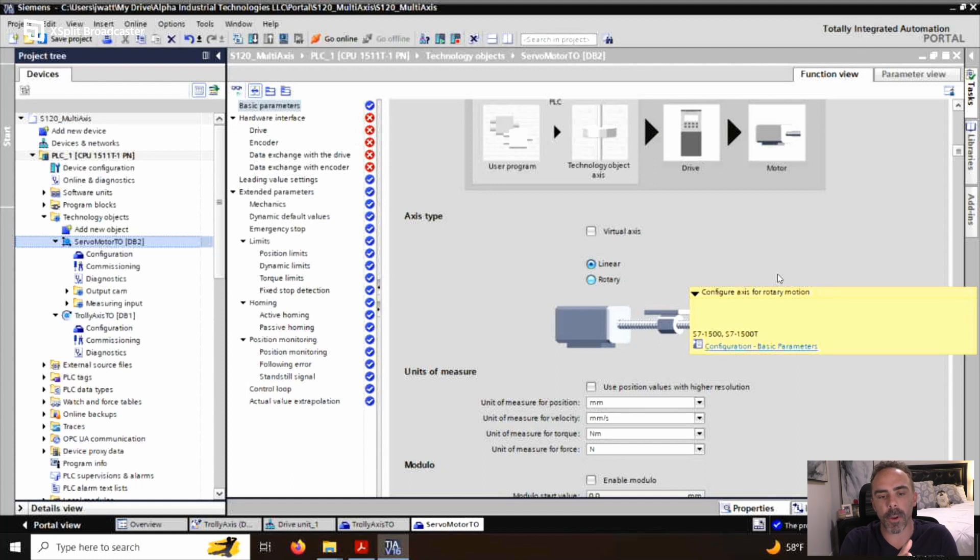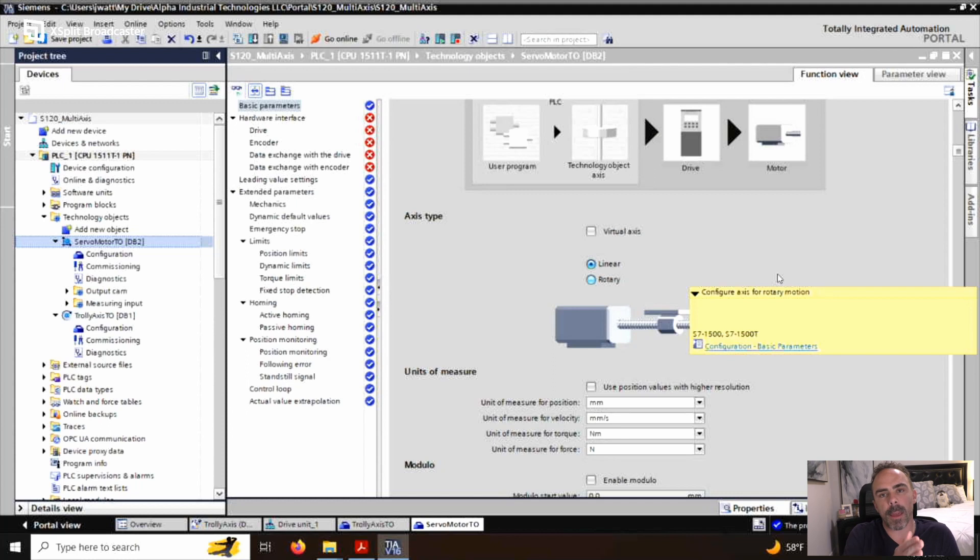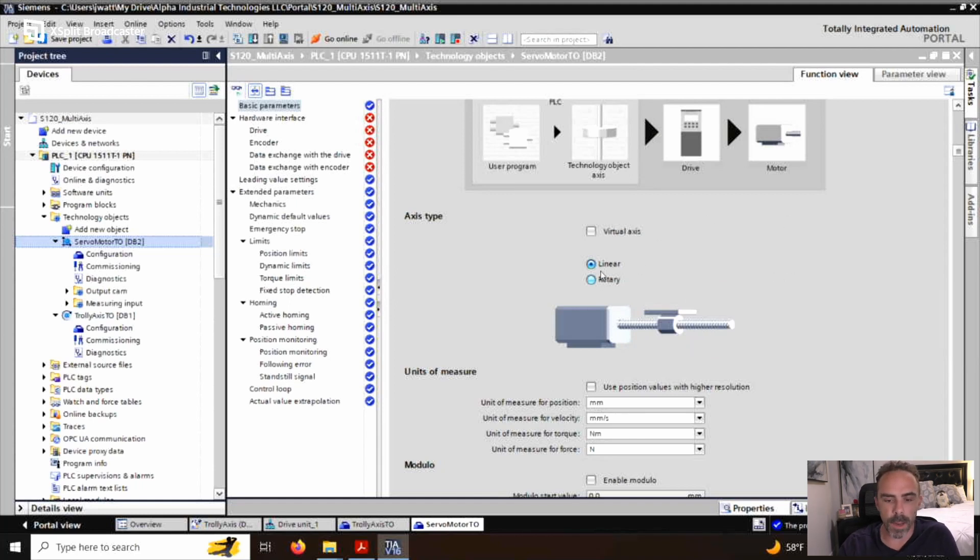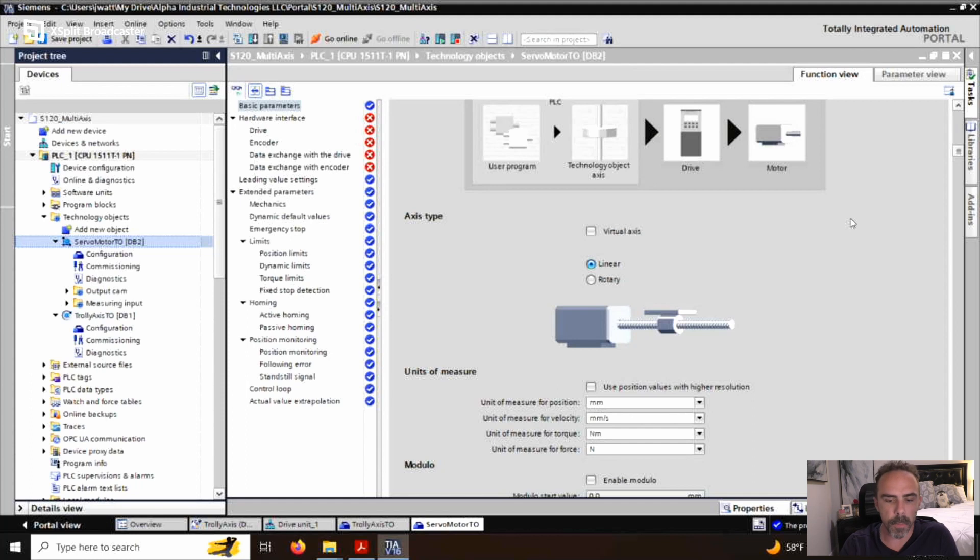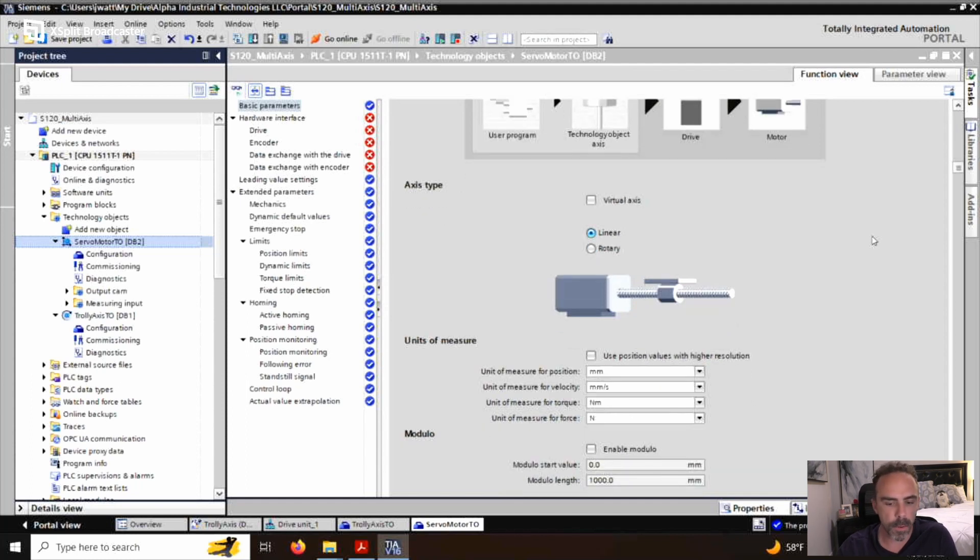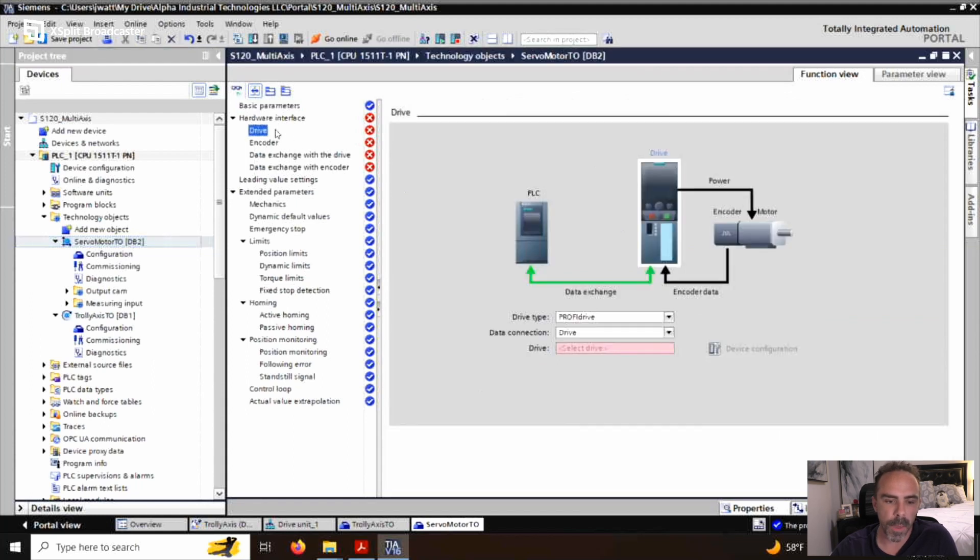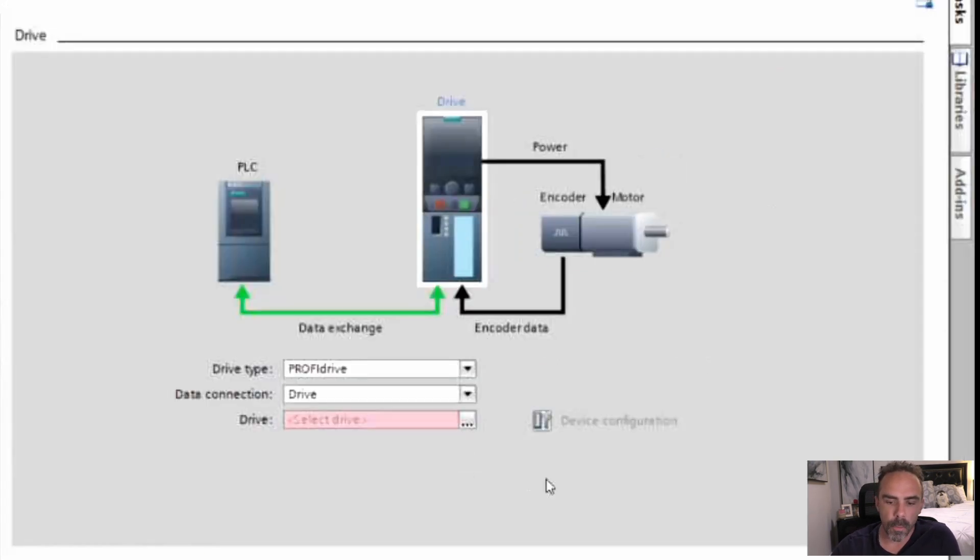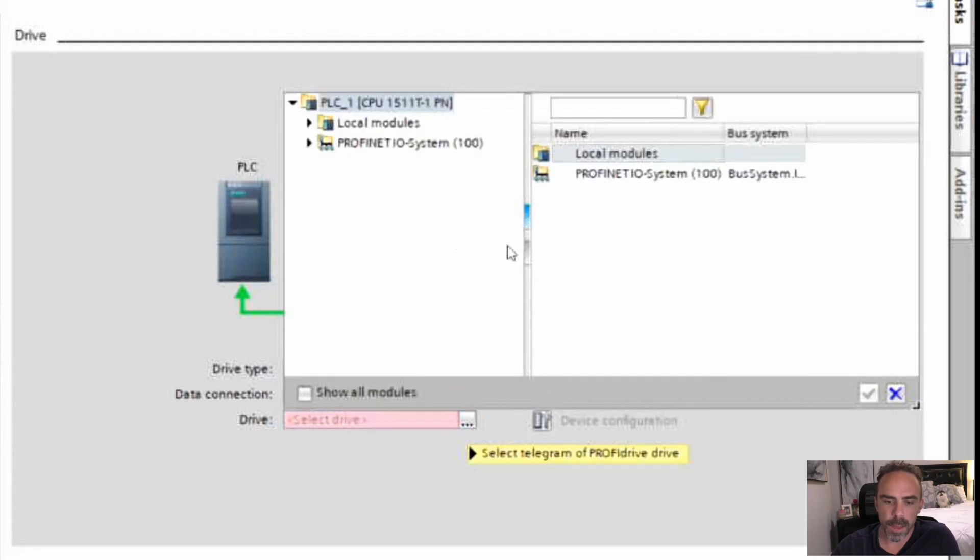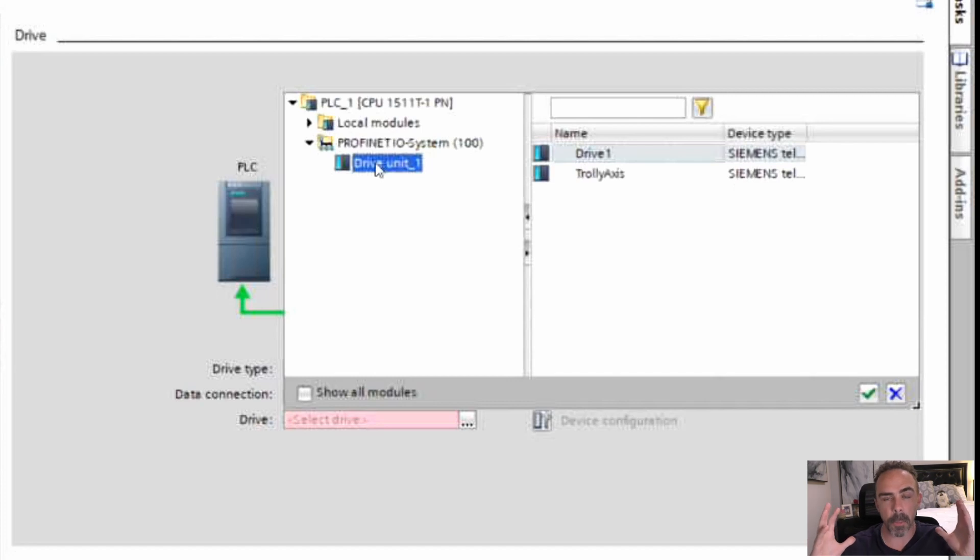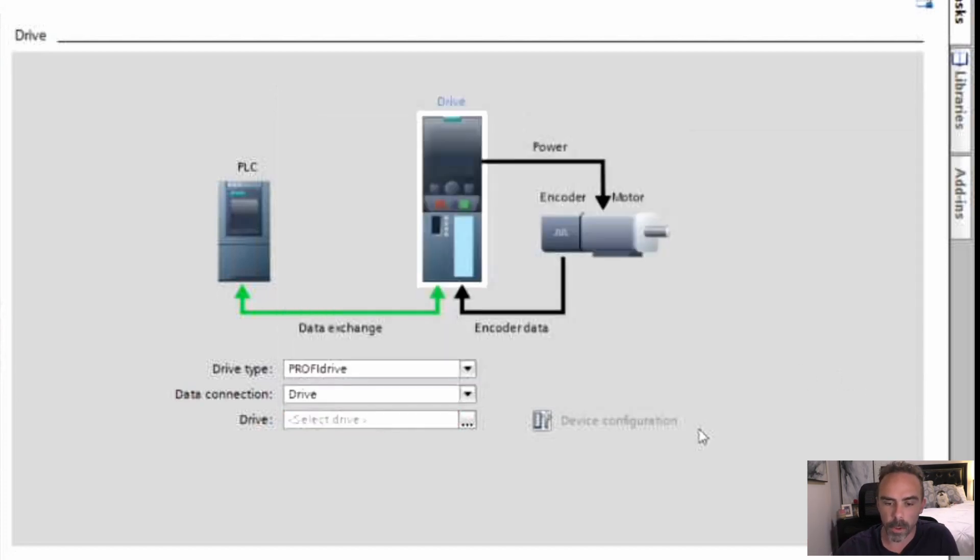One of the things about a positioning system is you need to know what type of motion you have. Are you going to be doing something in linear motion? Are you measuring something in millimeters, inches, feet, meters, or are you going to be measuring it in degrees? Because that's the difference between this linear and rotary. So for this one, we're just going to leave it as linear because we want everything in millimeters. Same thing here. We got these red X's over here. We go over to the drive and we're going to select the PROFINET system, go to that drive unit and we're going to select drive one and click check.